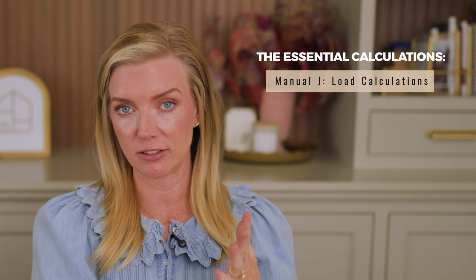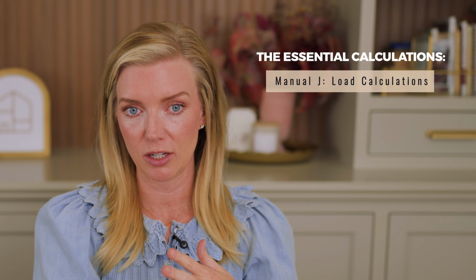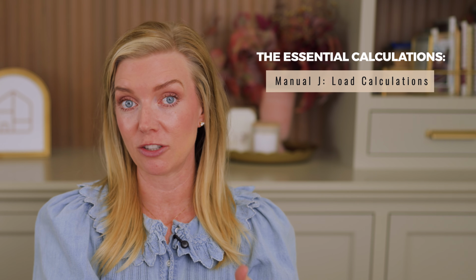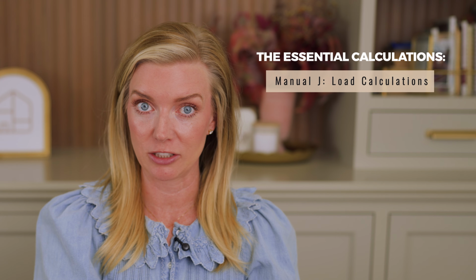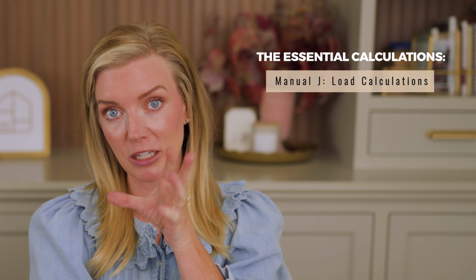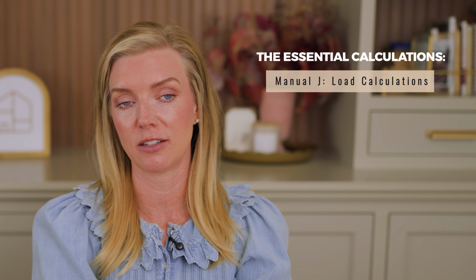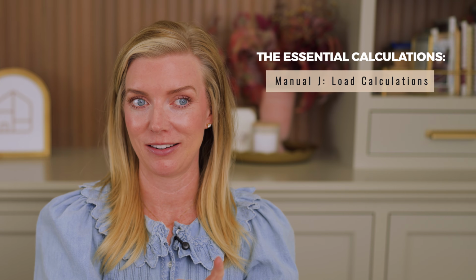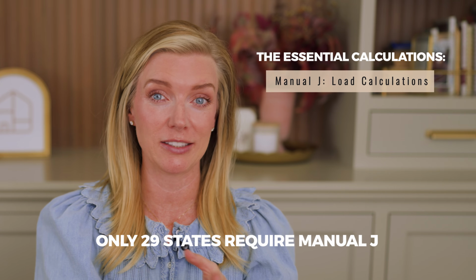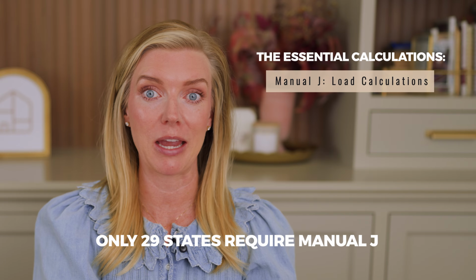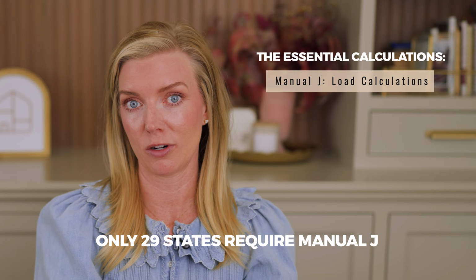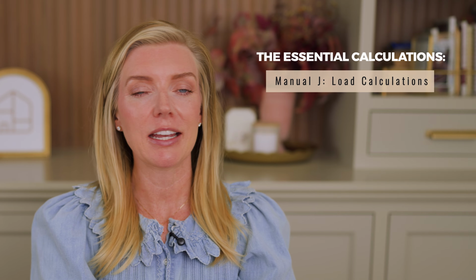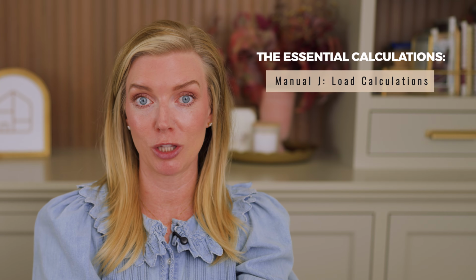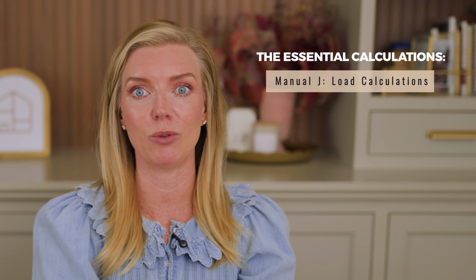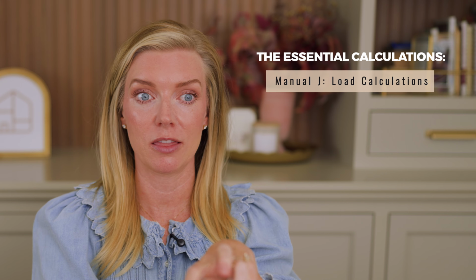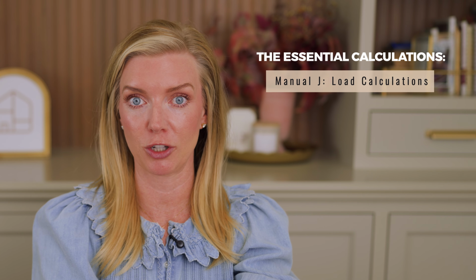there's a 2009 building code that came into effect requiring manual J calculations, meaning there would actually be load calcs for the project. But not every state has adopted that - I believe only 29 states require a manual J calculation for a new mechanical system. And even then, just a simple load calculation isn't enough data to determine the optimal mechanical equipment needed for your home.